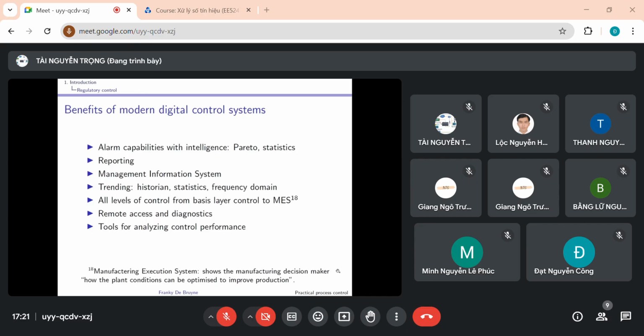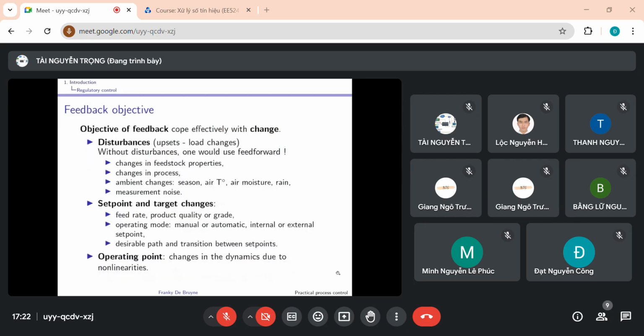Some of those systems will even propose tools for control performance monitoring. Each control loop will be evaluated in terms of tracking and disturbance rejection performance using key performance indicators. In this way, you can easily isolate the problematic control loops and you know where to concentrate the tuning effort. Some of these systems will even propose new tuning parameters.